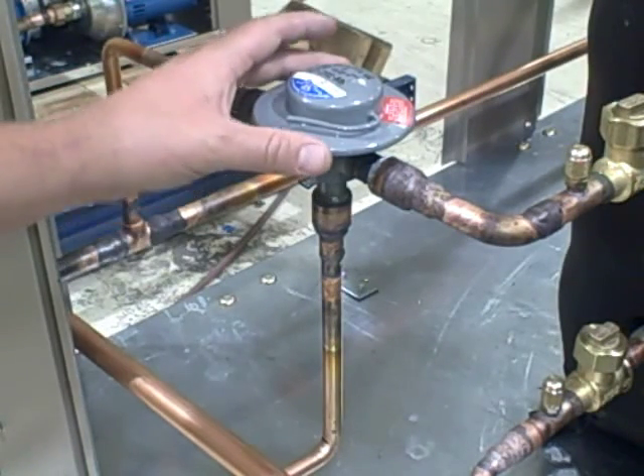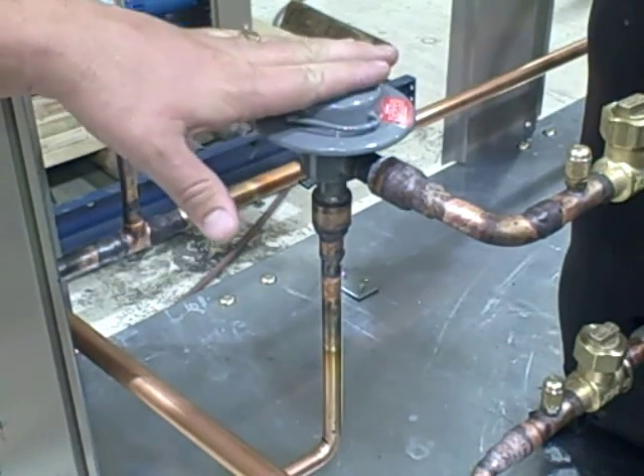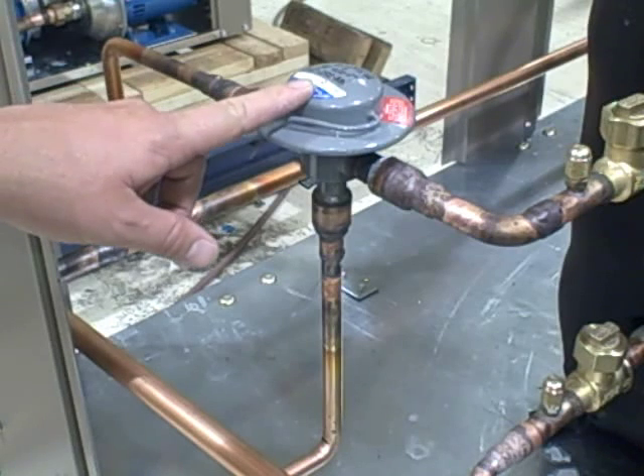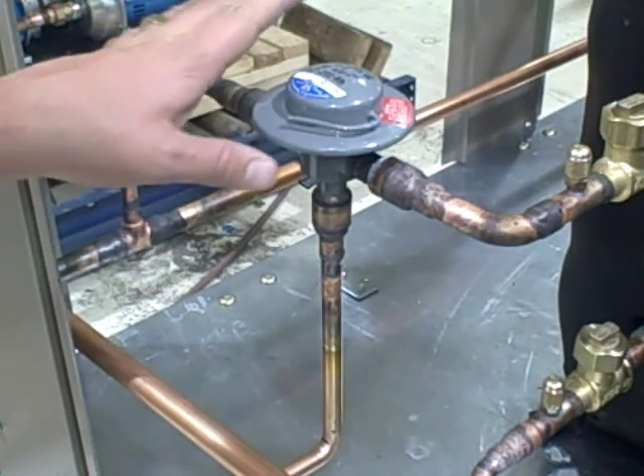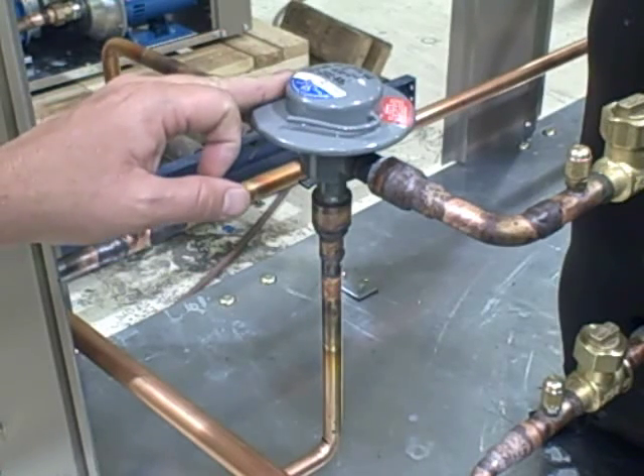This is a standard Sporlan flooded condenser valve. It's a very simple operation. This is your regulating power head. This is a non-adjustable valve. This valve is rated for 225 PSI, so if the head pressure is above 225 PSI, this particular valve will not do anything.